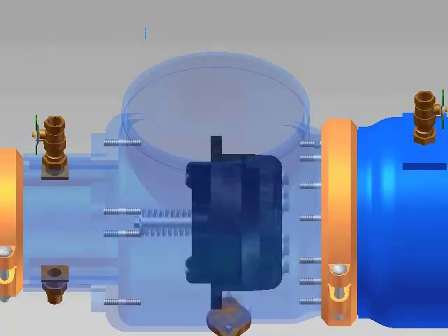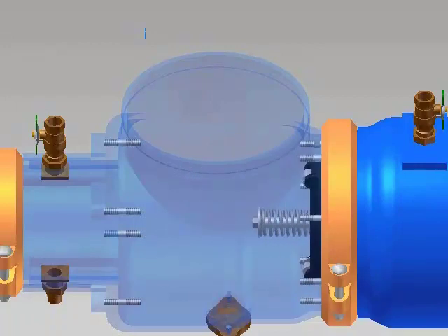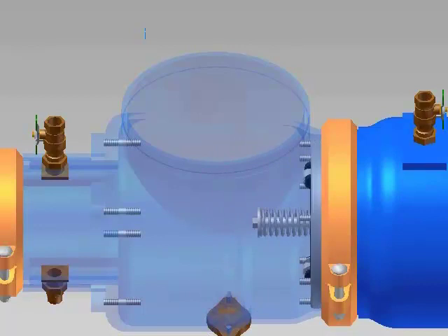After servicing the number 2 check, place it on the studs in the body. Slide the stainless steel retaining ring onto the studs. Place the seven washers and nuts on the studs and tighten the nuts evenly.